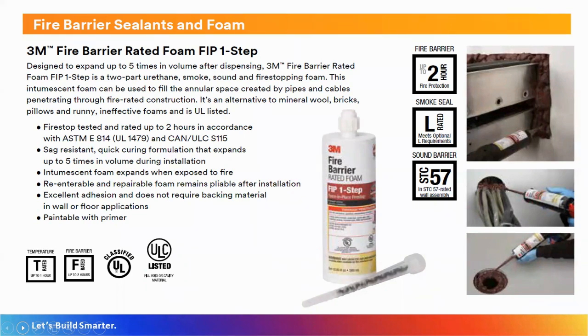As you can see from the picture here, this is a 2-component material, so it's dispensed through a static mixing tube. We have pneumatic caulk guns that are basically used for this. They're specialized guns, and if anybody is interested in the FIP One Step, we can get you information on the related accessories as well. This is an intumescent foam that remains pliable over the service life of the product. So if you needed to go back into it to, say, pull more cable, you could just take an insulation knife, cut a hole in it, and pull your cable. If you had any remaining cured foam, you could stuff it back into the opening, and then any gaps or voids can be resealed with fresh FIP foam.